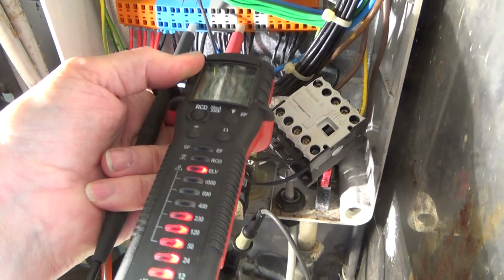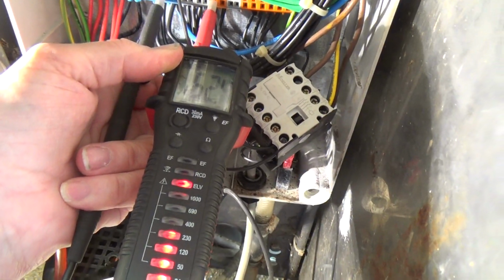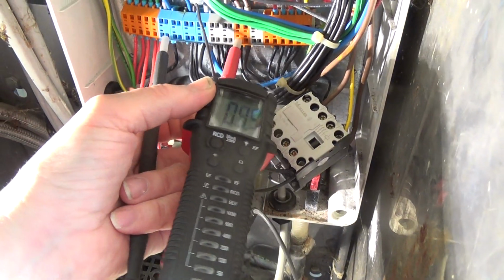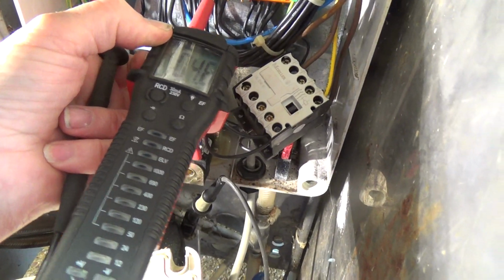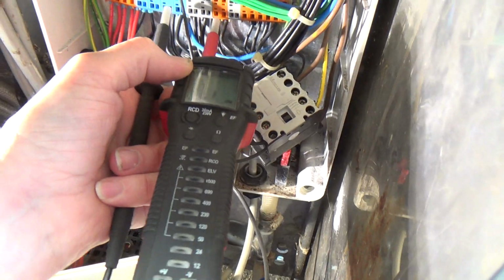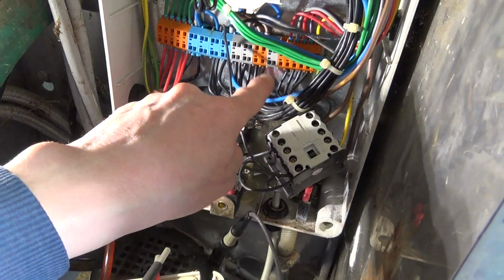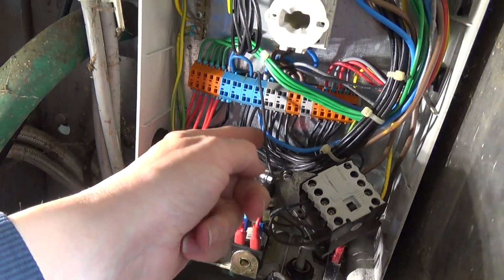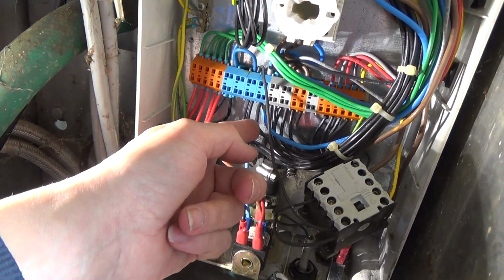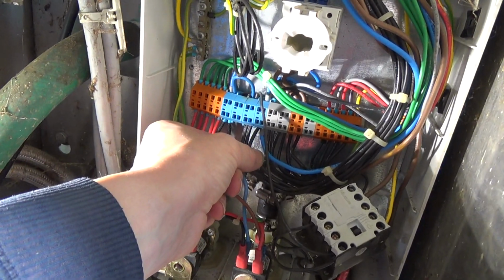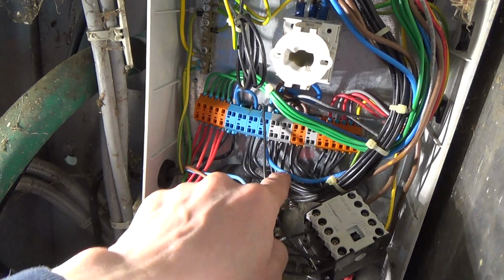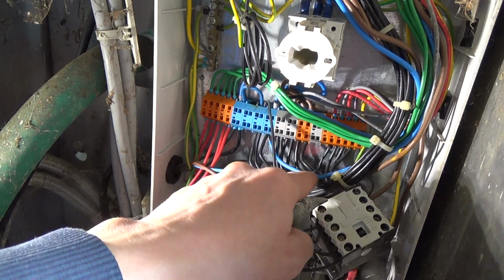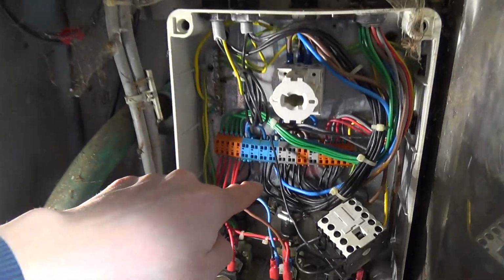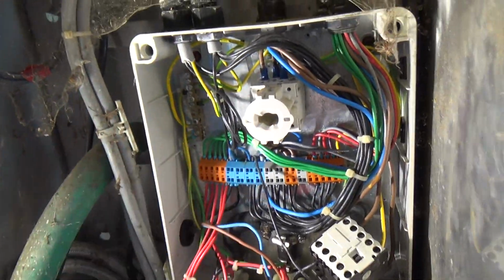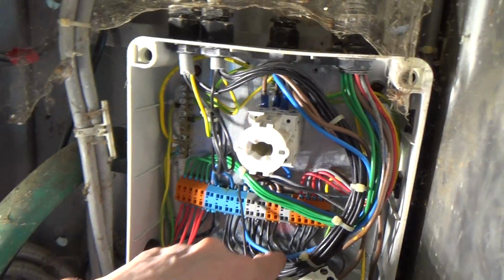Now if I go onto this one, we're only getting 162 volts because we haven't got a proper neutral. We haven't got a proper neutral, but that is a proper incoming neutral. It's probably this wire here. Then we've got two lives. So that neutral wire that goes up to this box is off of the incoming. It's before the switch. So even though we've got the switch off, this isn't isolated.